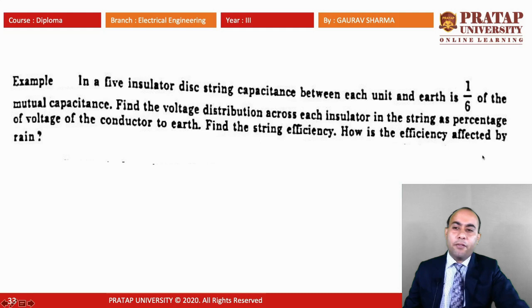Now, let us take an example. In a 5 disc insulator string, the capacitance between each unit and the earth is 1/6 of the mutual capacitance. Find the voltage distribution across each unit in the string as a percentage of the voltage of the conductor to earth. Now, what we have to calculate? We have to calculate the string efficiency and how the efficiency is affected by rain.